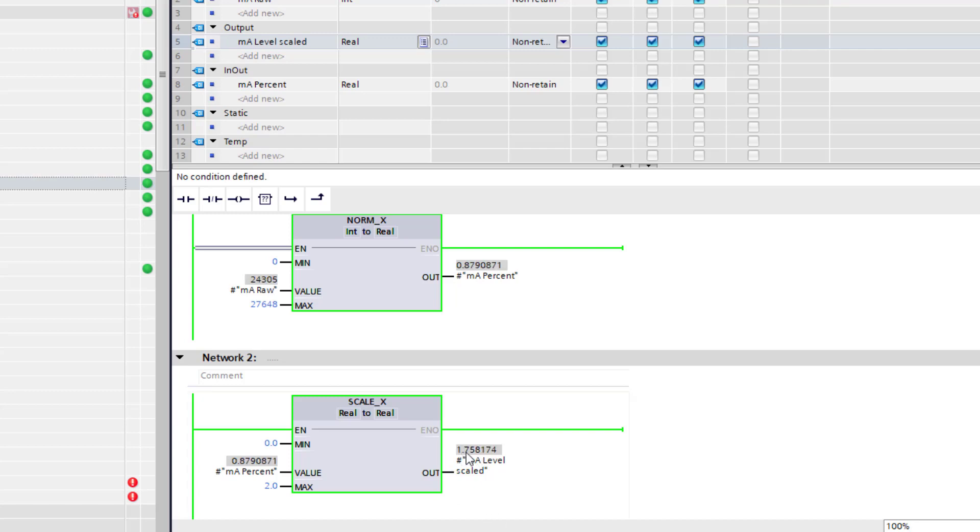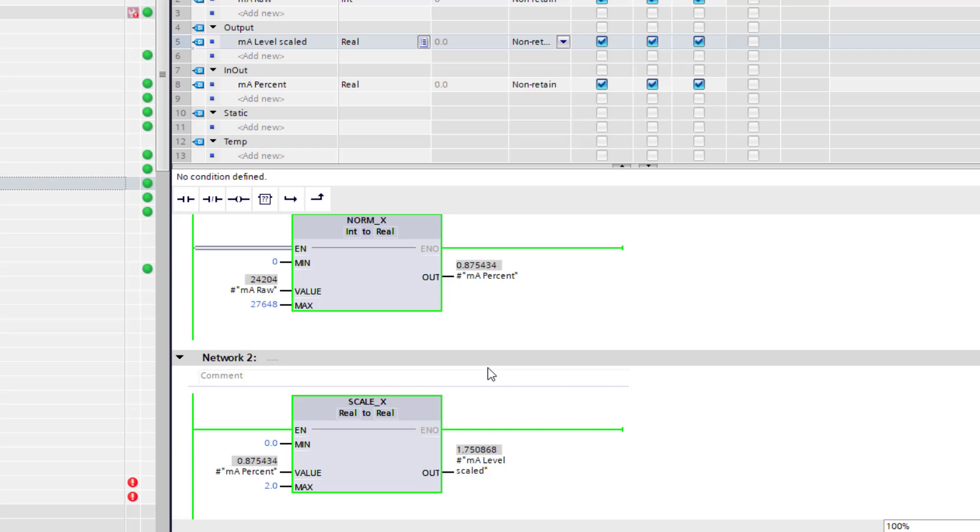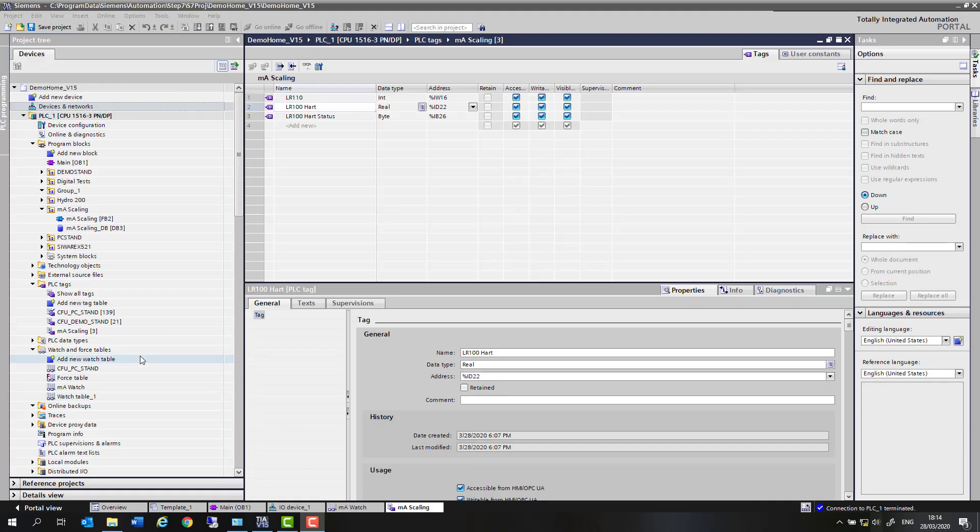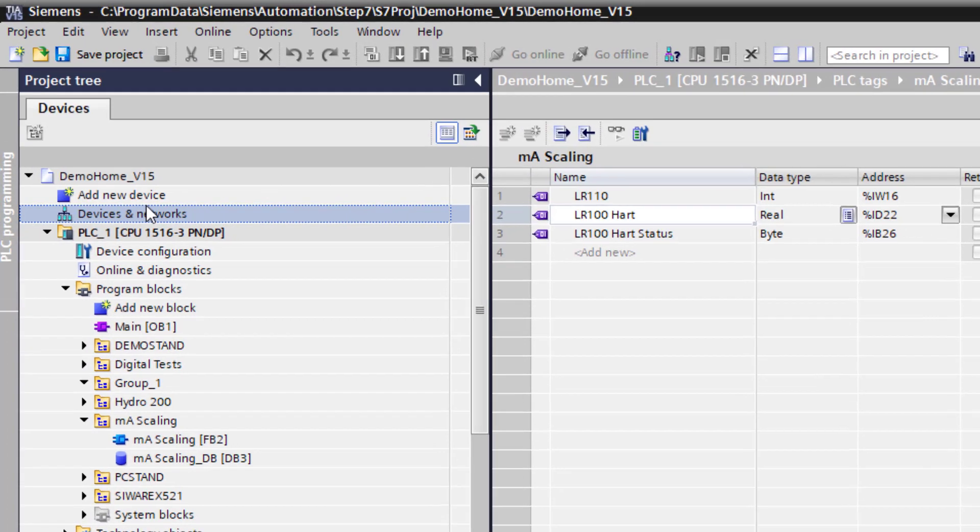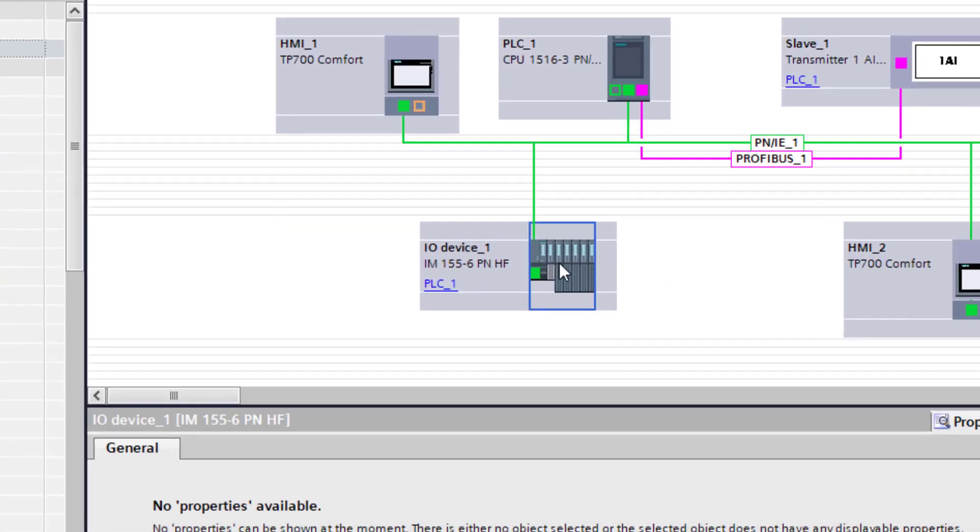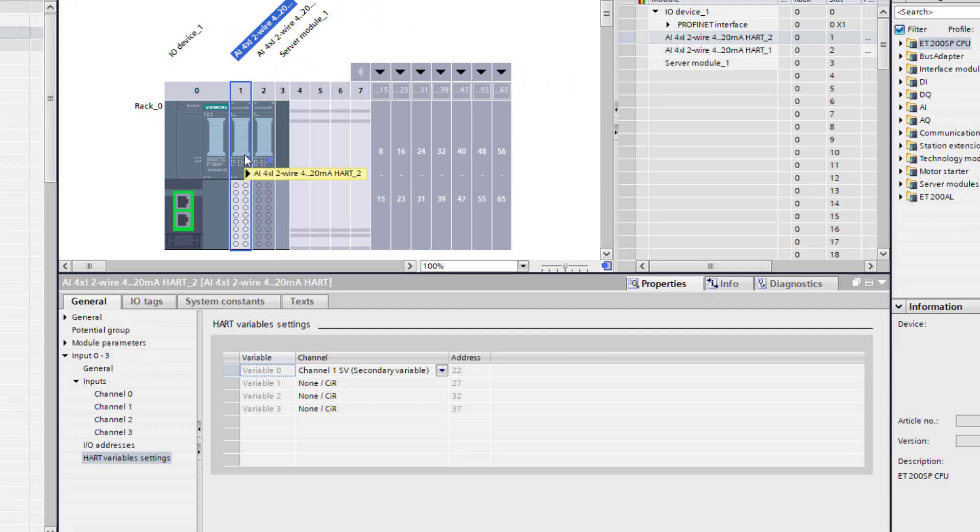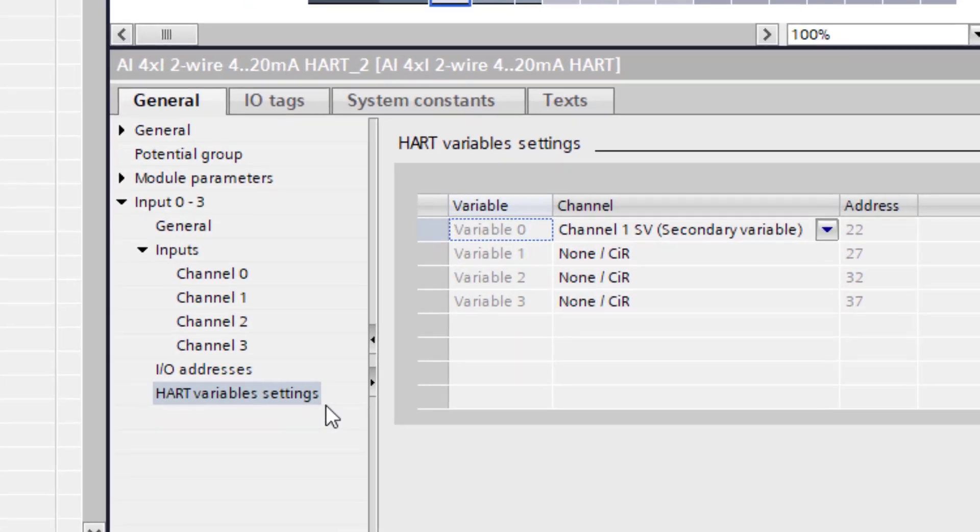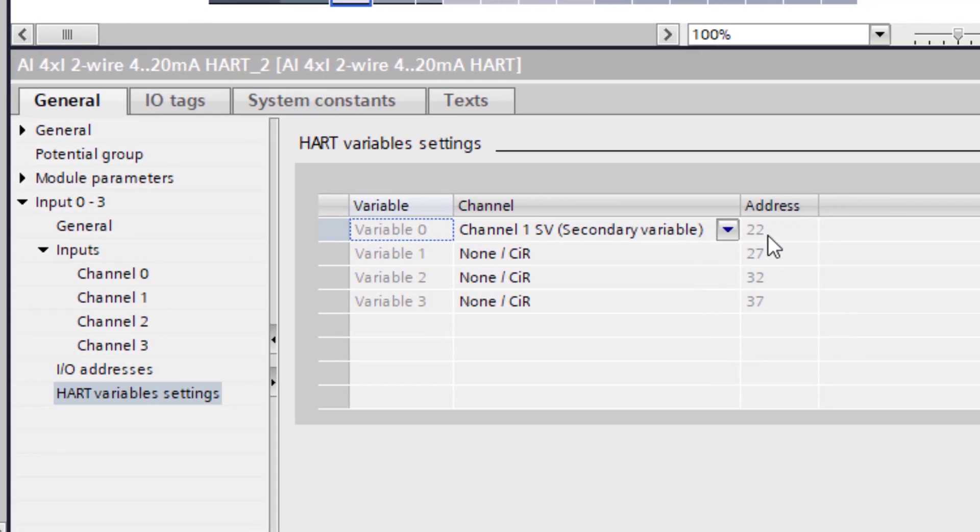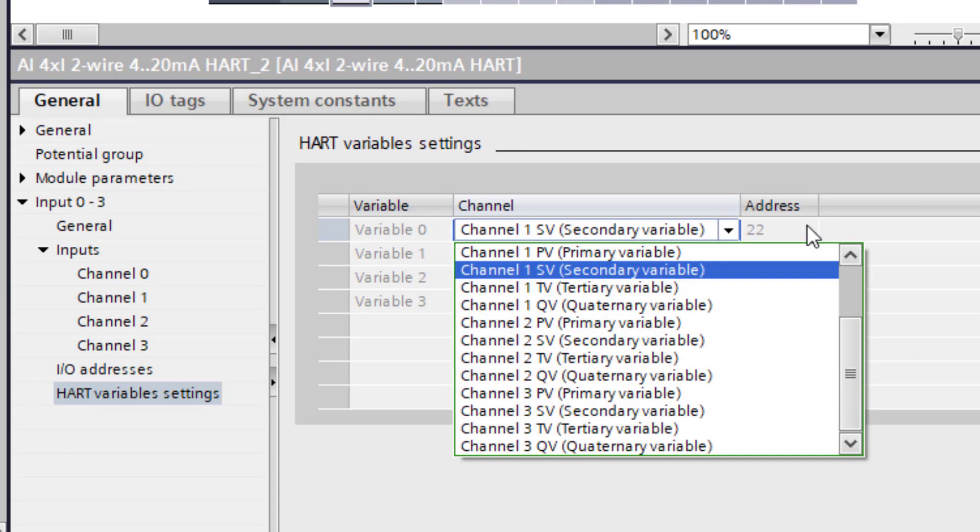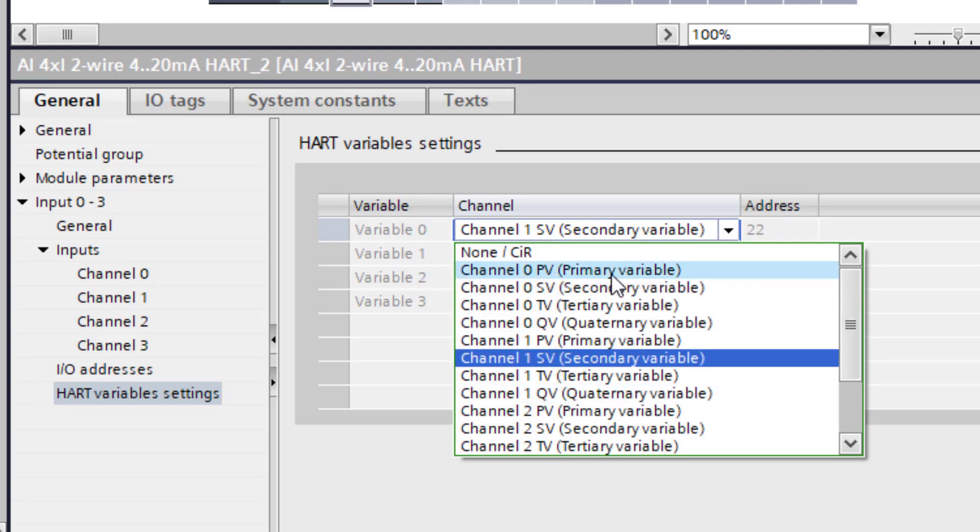So what I'm going to show you next is how we can miss all of this out. And if we're not after a fast-reacting application, how we can just read the HART value straight back from the device, which is more accurate than a scaled milliamp input value because of the resolution of the analog-to-digital conversion on the PLC card. If we have a look at our card back in the hardware screen, and I go to the input card at the bottom, you'll see your HART variables. Over the right-hand side you've got your start address because it's reading HART, it's a real double word. And from here you have a table. So these are your channels physically on the card where you're wired to. So I'm wired to channel one.